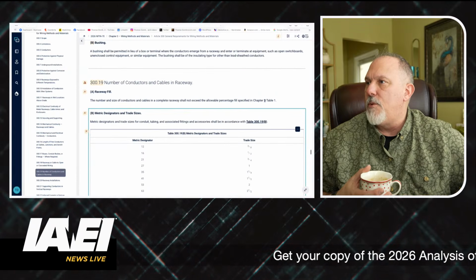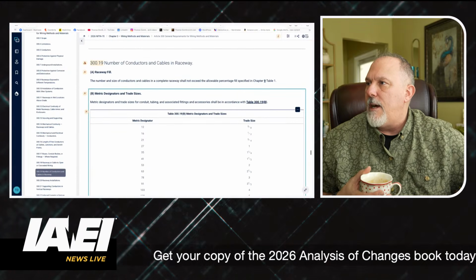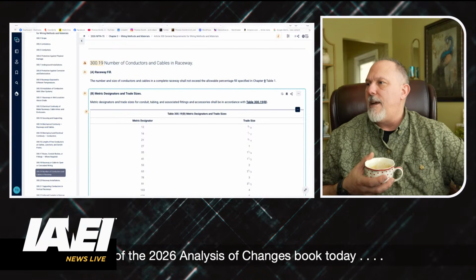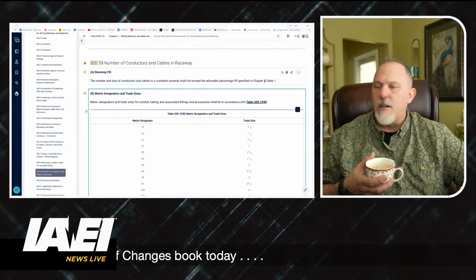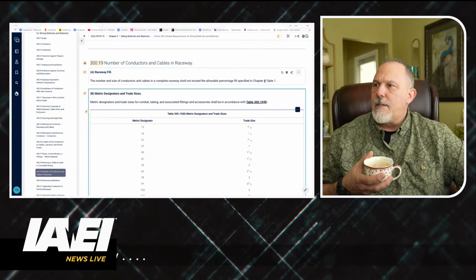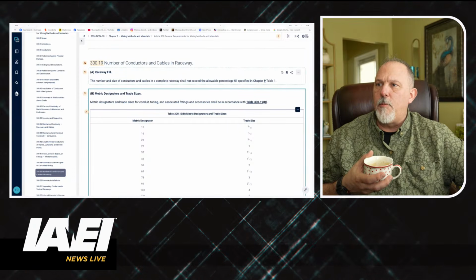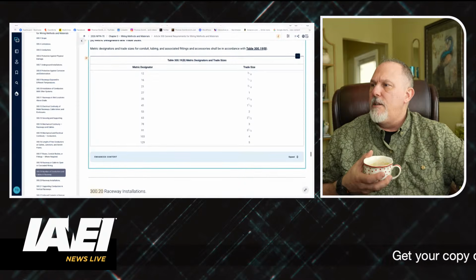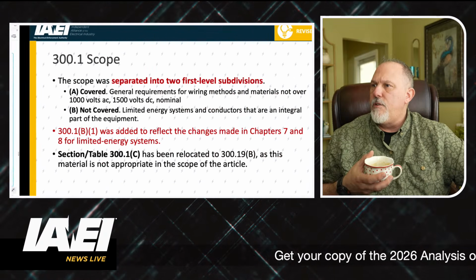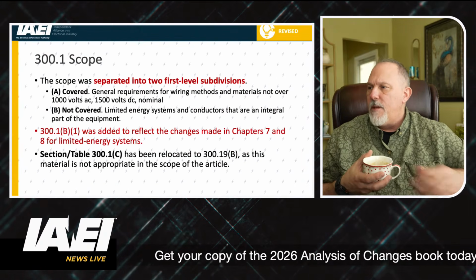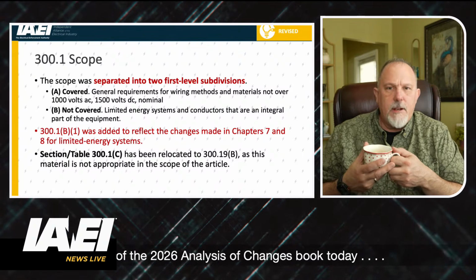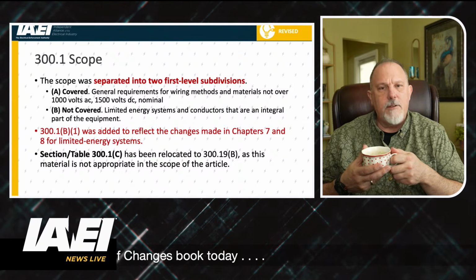So that's the table that they relocated, and it looks like they added raceway fill, the number and size of conductors and cables. Complete raceway shall not exceed the allowable percentages in Chapter 9, Table 1. So they moved some stuff around. So the section in the table 300.1C has been relocated to 300.19.